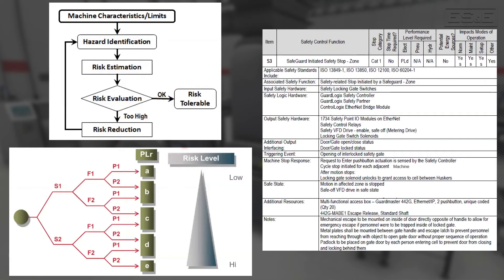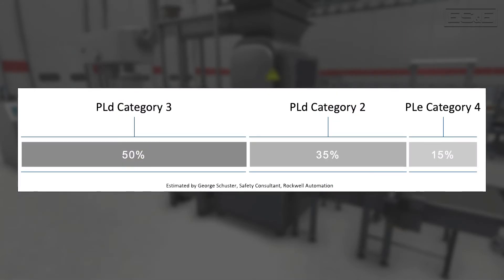Rockwell did a market assessment to understand the category and performance levels for the machinery being designed and installed in industry in order to understand the SIL ratings needed for the equipment they provide. The result of the estimation was 85% of machinery needs to achieve a performance level D and not performance level E, which is the highest safety rating. Therefore, if the end goal is to achieve a specified performance level, we need to design the system based on the category and SIL components.